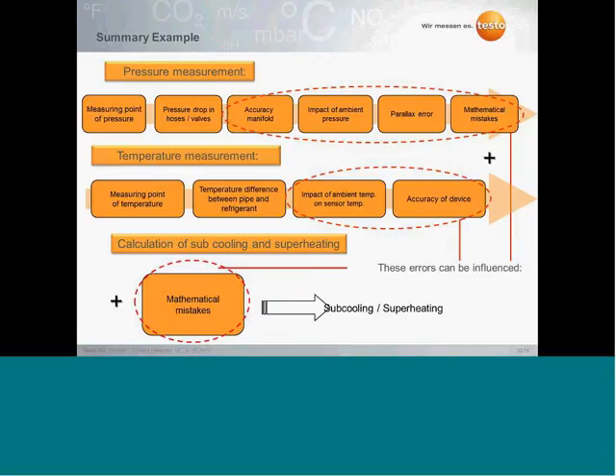We can use manifolds which measure the absolute pressure. So depending on whether you are at sea level or in the mountains, our digital manifolds will check the surrounding absolute pressure and calculate the values. We have no parallax error, and of course the risk of mathematical mistakes is much lower, as a lot of the values are directly calculated by the manifold itself.